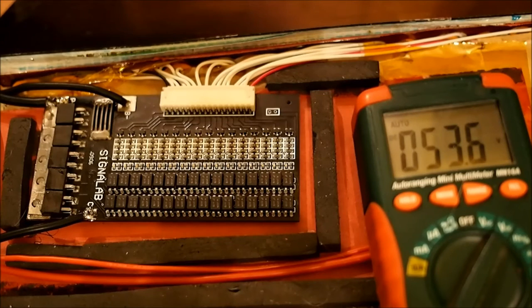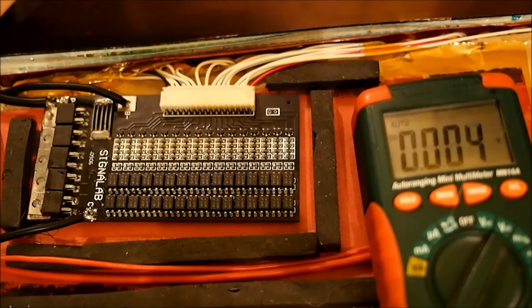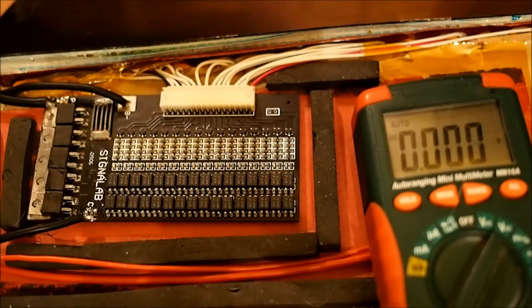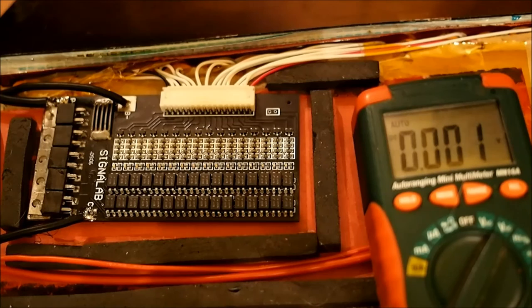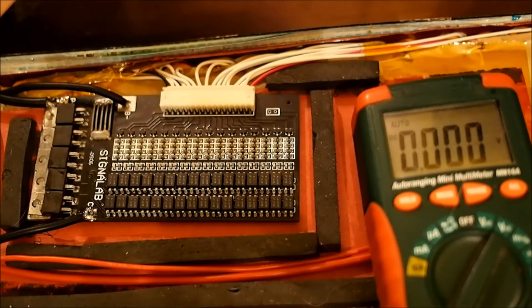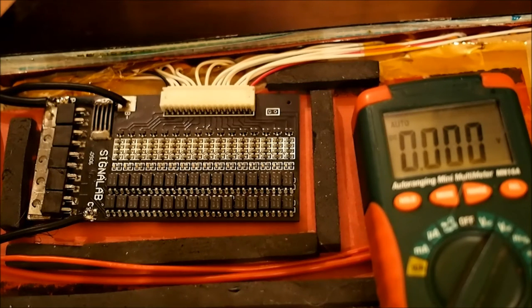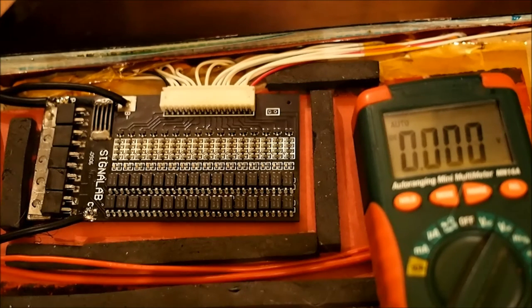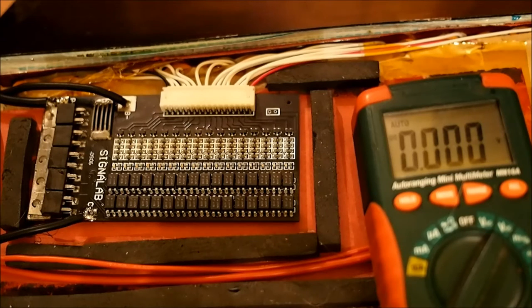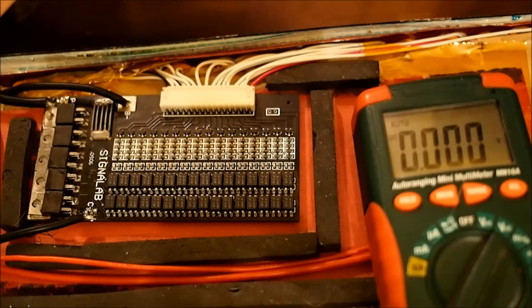Now, so you're going to want to verify that not only are those voltages the same, but that they are full battery voltage. If you have a 48 volt battery and it's only delivering 42 volts on the discharge terminals, then there is something wrong.